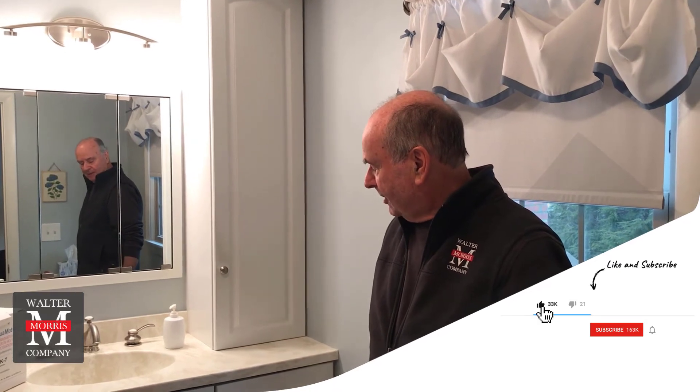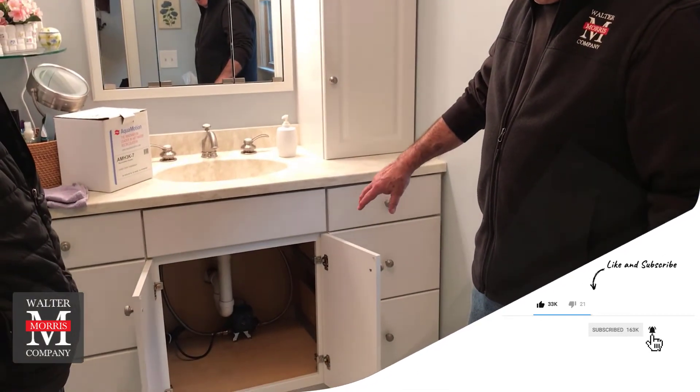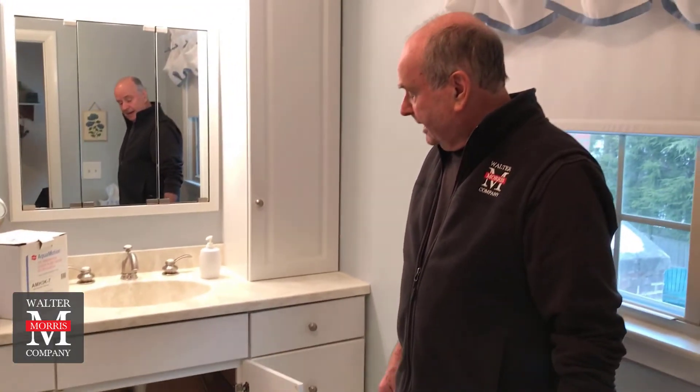It looks like we've got a successful operation and installation here today, thanks to Joey Bonang of JB Plumbing and Heating, Warwick, Rhode Island. We've got the timer set up and plugged into our GFI outlet. The pump runs and draws about 0.6 amps when running. AquaMotion has estimated that for an average household it's probably worth about three dollars a year in actual electrical cost for keeping hot water up at the top. Thank you very much.